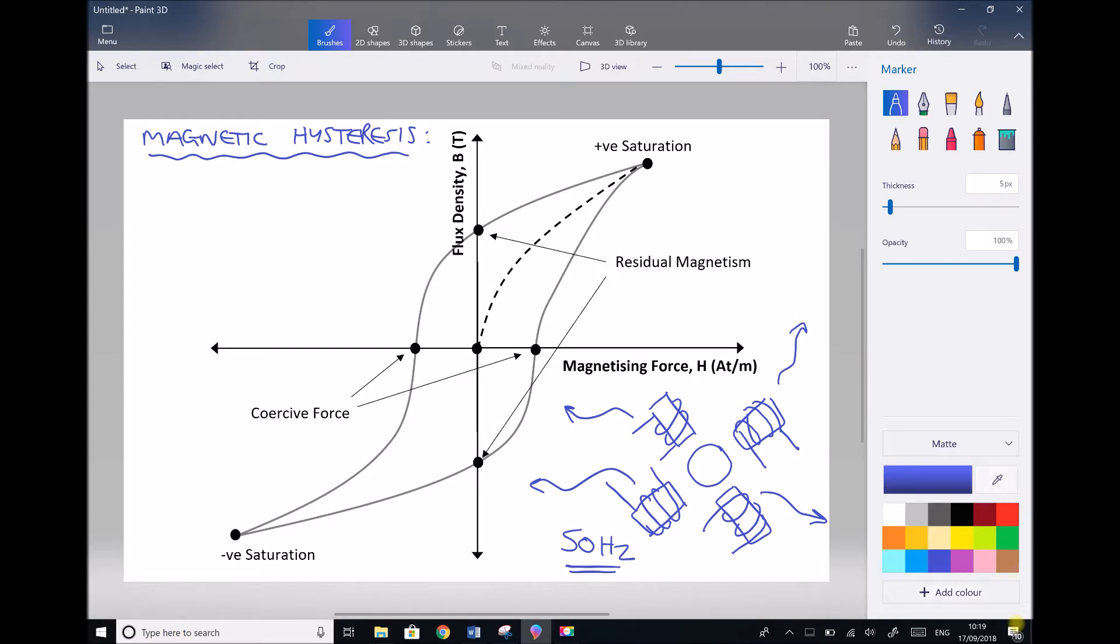But the important thing here is what happens to that material over time. We've studied the impacts of thermal shock, and whilst this generator is in operation we're going to expect the poles of our generator to become hot. If that generator is then turned off for any length of time then we're going to see that temperature reduce. So there is the potential long term for some deterioration or thermal degradation of the poles of our stator.